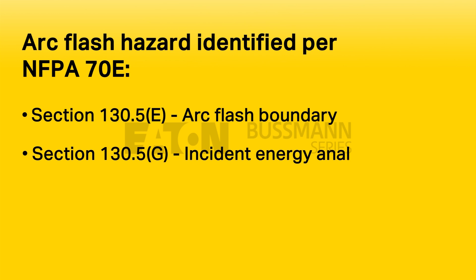NFPA 70E, the standard for electrical safety, should be consulted, and proper workplace safety practices should always be followed. The arc flash hazard can be identified per NFPA 70E section 130.5(E) for the arc flash boundary and 130.5(G) using the incident energy analysis method. The information provided uses the simplified fuse formulas based on IEEE 1584 Guide for Arc Flash Hazard Analysis, and also found in NFPA 70E Annex D. These formulas were derived from actual test data using Bussmann series Low-Peak fuses.